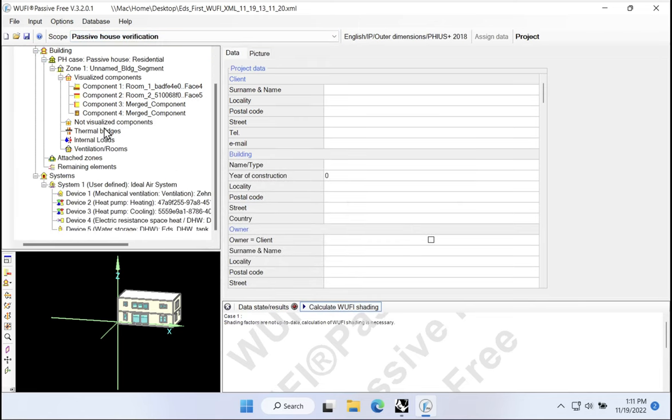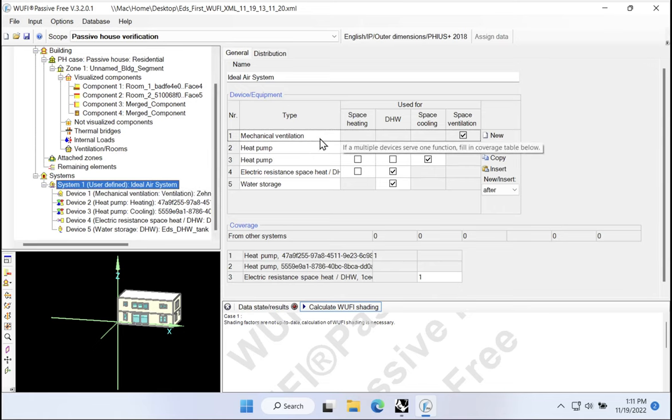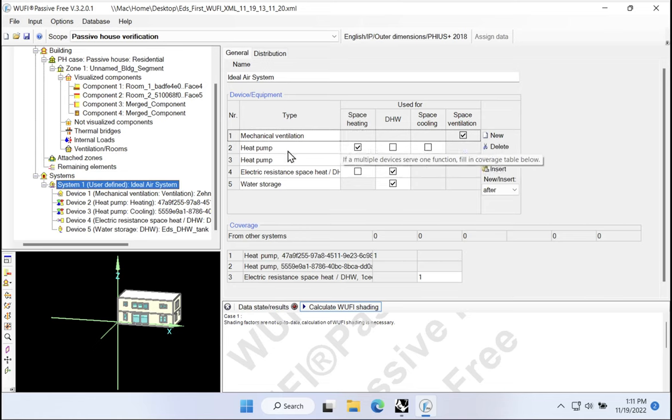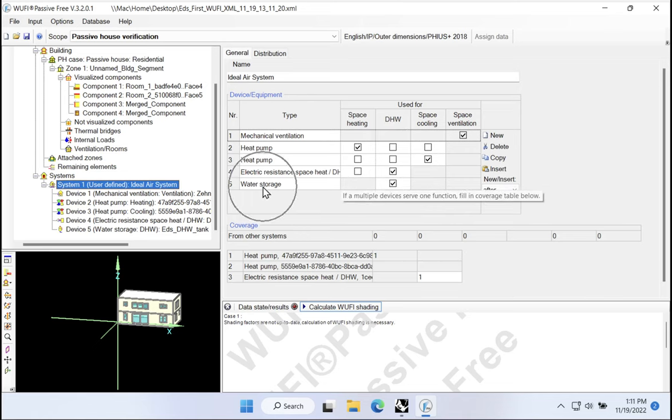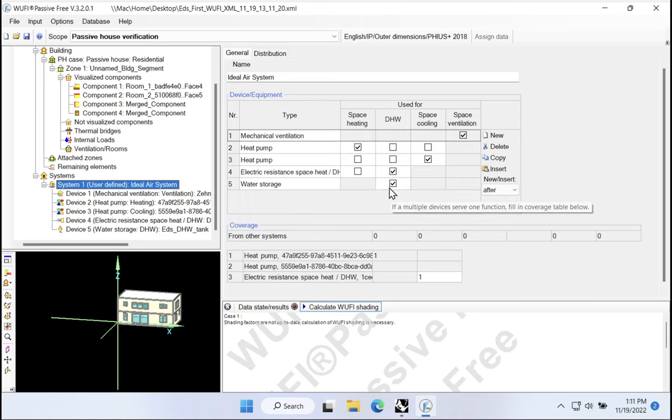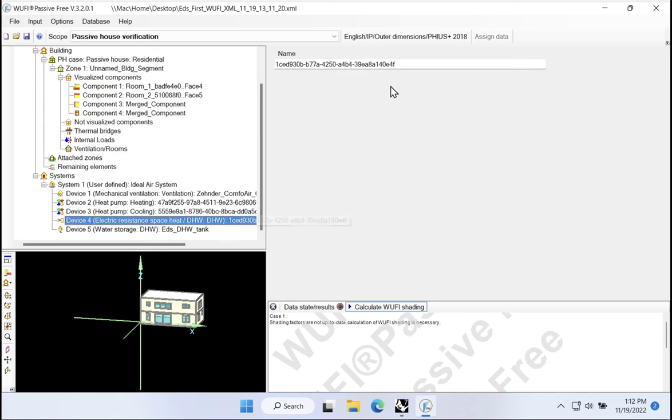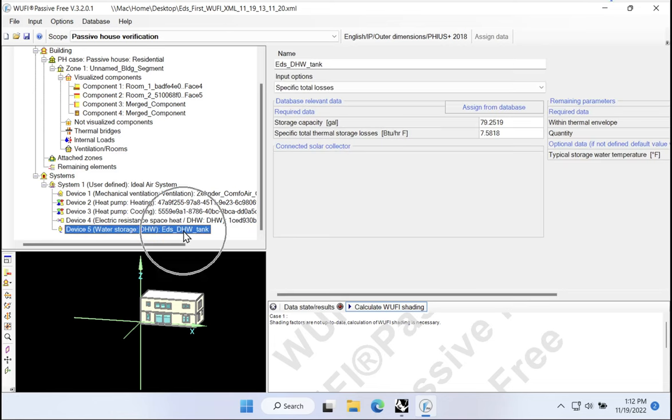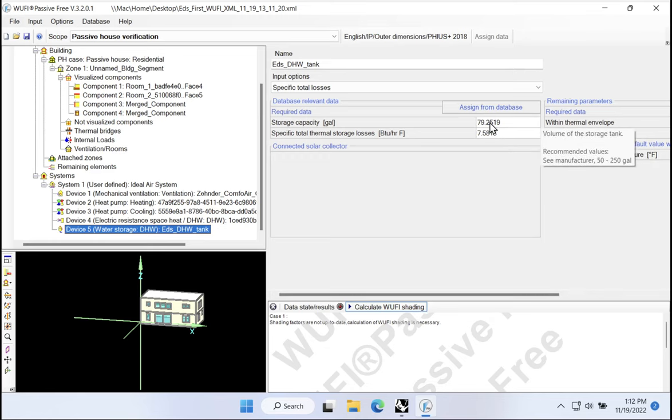And I will navigate to the desktop. I'll say file open, go to my desktop and filter for XML files. Open up the one with the newest timestamp there. Say OK. And let's see what we have now in our systems. We have our ideal air system here. Our ideal air system has mechanical ventilation, obviously. Heat pump for heating. Great. Heat pump for cooling. Awesome. And electric resistance heating for domestic hot water. And a water storage system for domestic hot water.